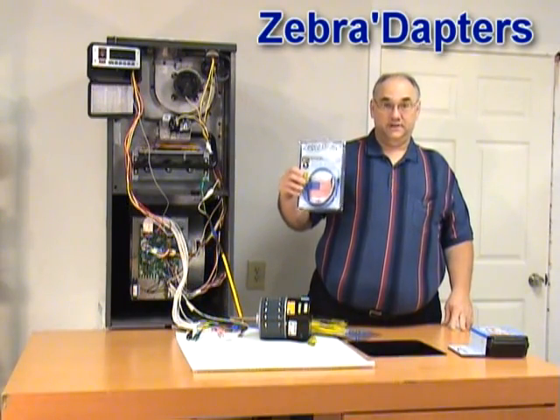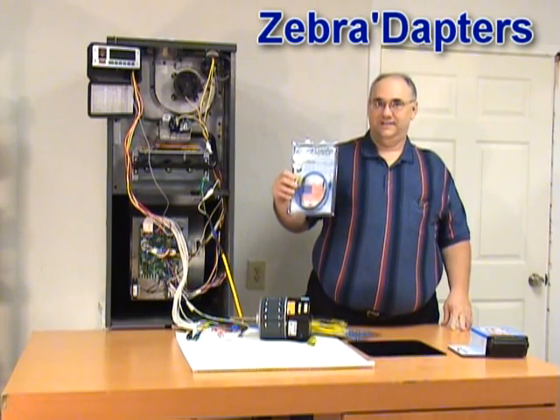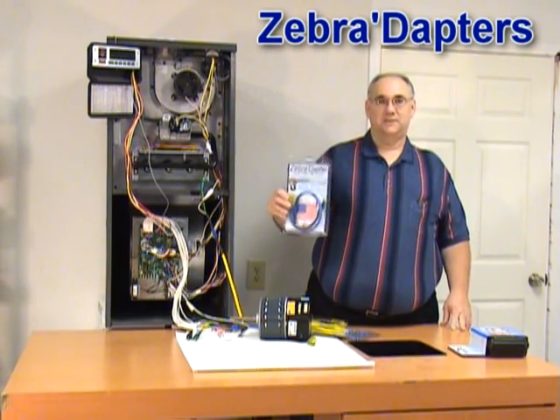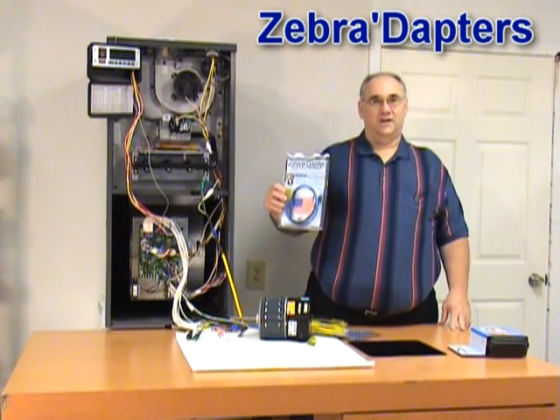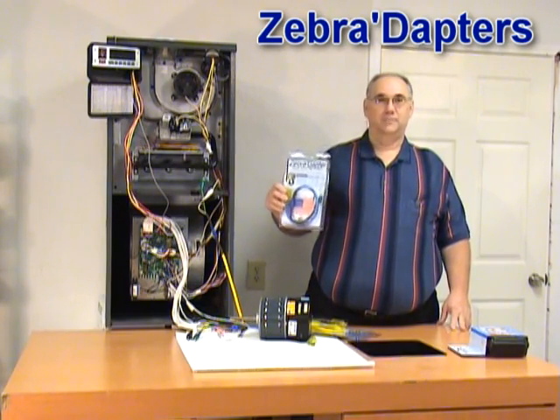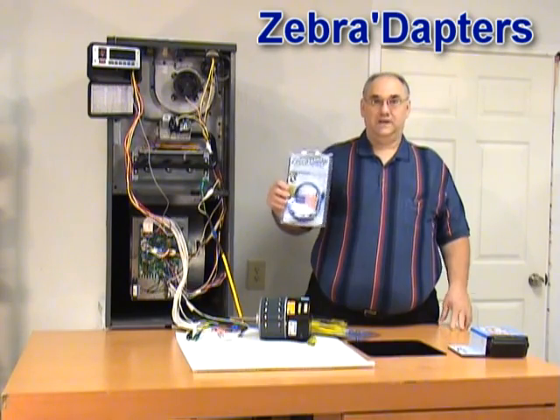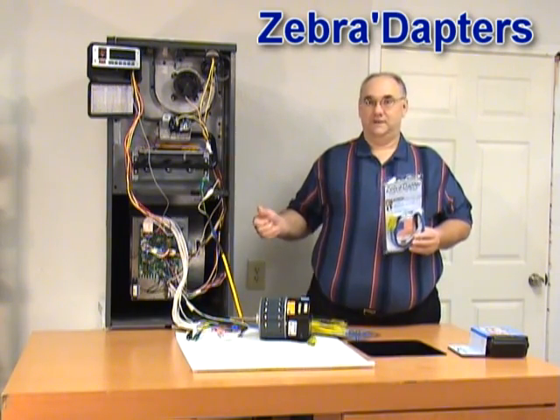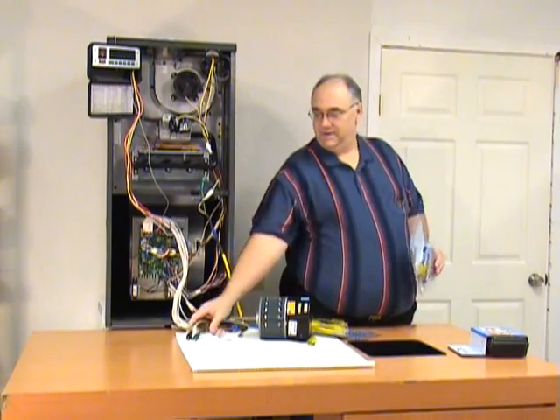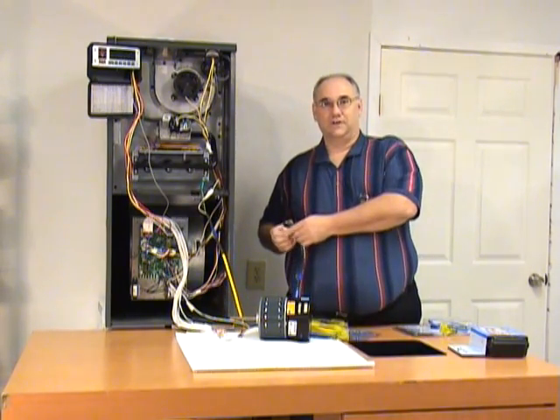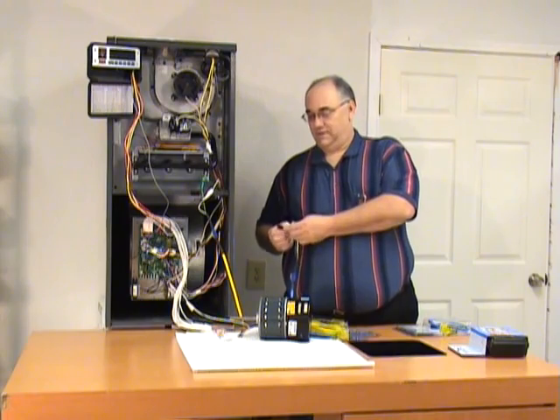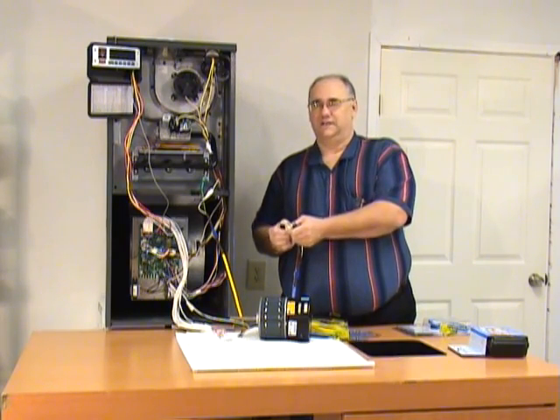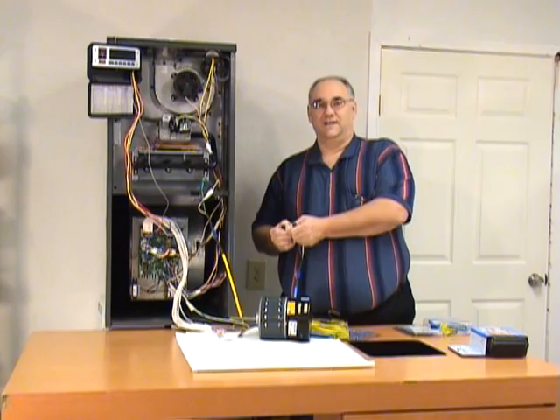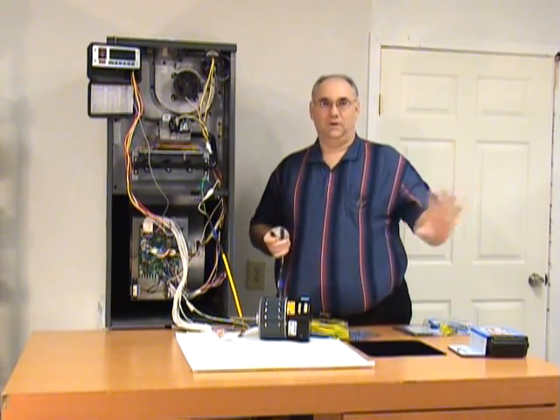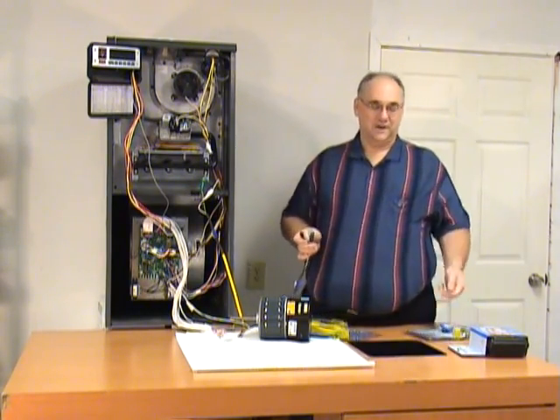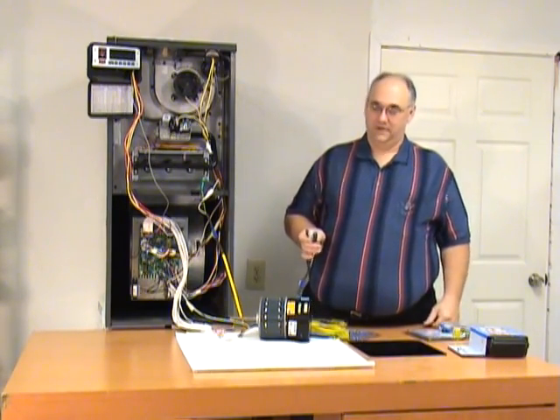I know none of you techs have ever done this, but you probably all heard of somebody who's done it. It's hot. It's a Texas summer afternoon. It's the last call of the day. You're out there ready to put your vacuum pump on a system and pull a vacuum, and you're tired, you forget about it, you're sweaty. You hook up the alligator clips on your little cheater cord so you have power for your vacuum pump. You hook them up to the contactor and you accidentally forget, oh darn, 240 volts. You've blown your vacuum pump. You hear the vacuum pump make a horrible noise when you start it and you know what happened.